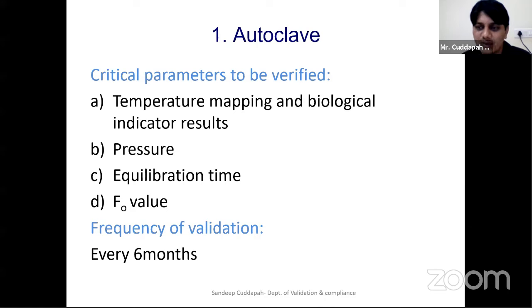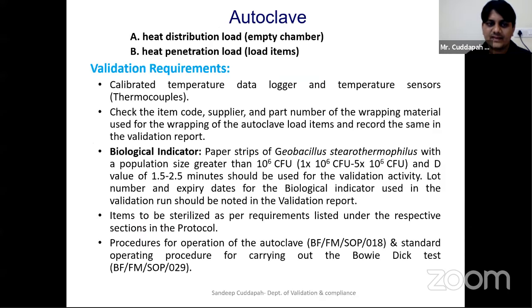So first list the core parameters of your equipment, and based on the core parameters, you can decide your frequency of validation. For some equipment, even the guideline itself states the minimum requirement for qualifying. For some equipment, you can decide based on your usage and your process criticality, the frequency of validation. As I told you, we use this autoclave for sterilizing the materials. These are some deeper things related to sterilization.